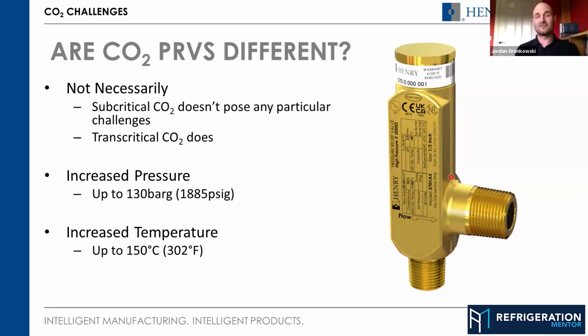A thing that comes in consideration there is the seal material as well. You tend to find most high pressure CO2 valves are Teflon or a derivative thereof in the seal material, whereas at lower pressures you can get away with softer seals with better leak tightness because again there is not as much force acting on the seal because the valve's not set quite as high.